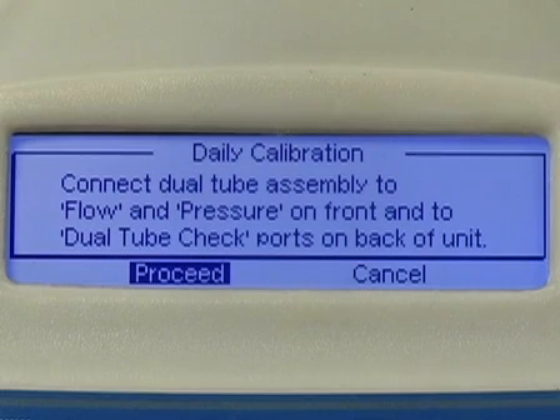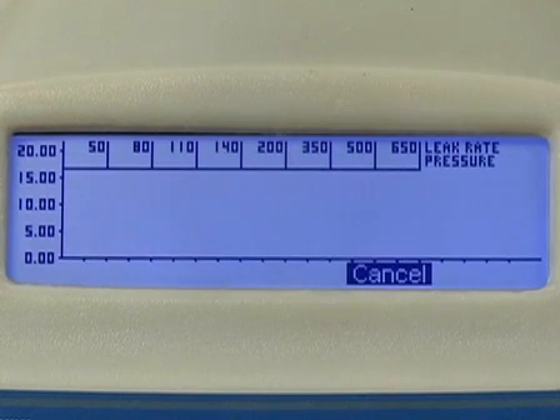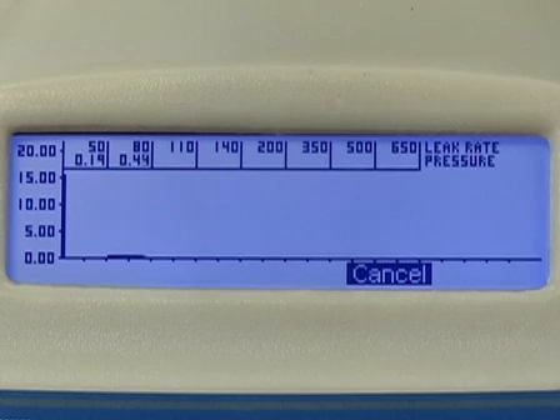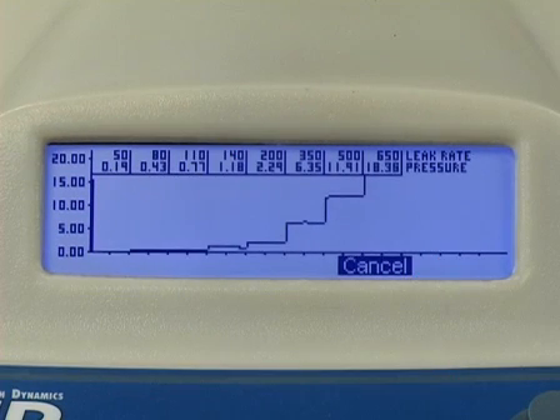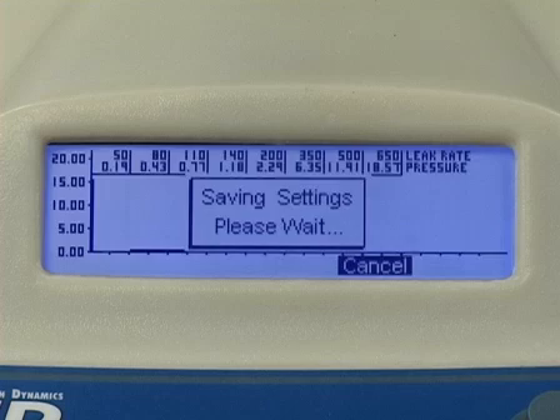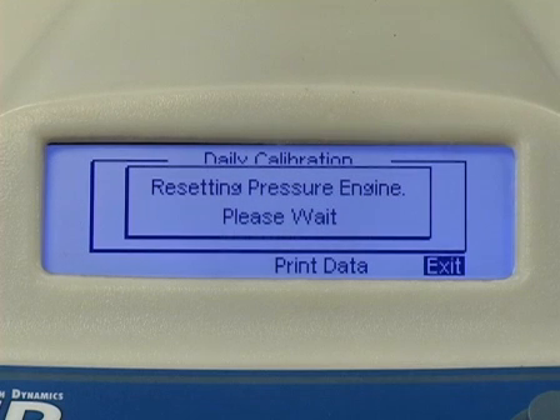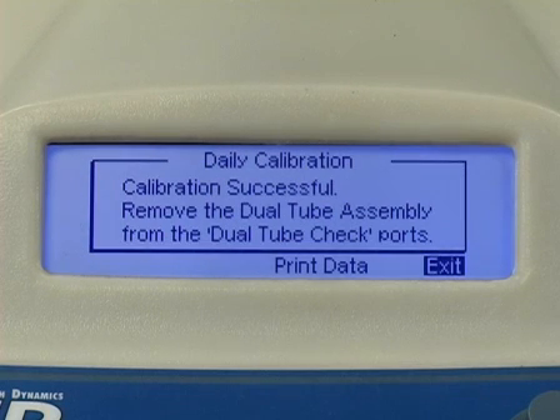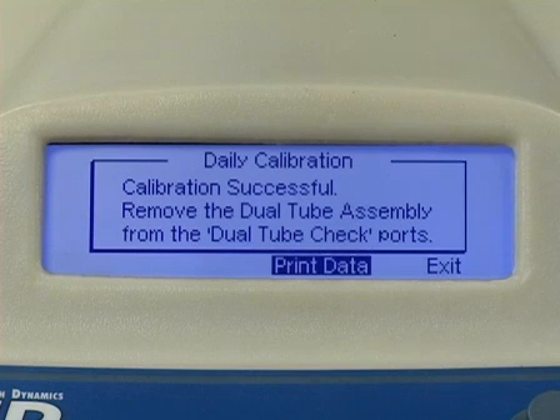Now you're ready to begin the calibration. Press the knob to begin the calibration. The dual tube calibration will run 8 different flow rates and will take approximately 1 minute to complete. This calibration confirms that the Quantifit is operating properly and within specification. When the calibration is complete, the results are saved into the internal memory of the Quantifit. The Quantifit stores only the most recent calibration.